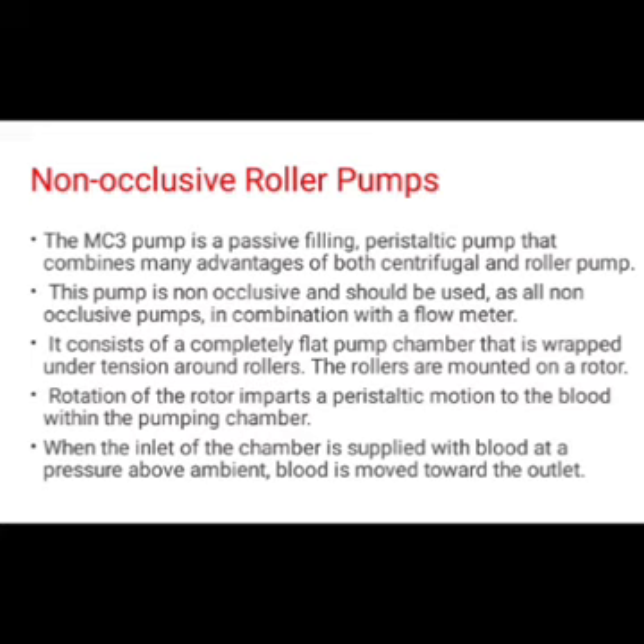Non-occlusive roller pumps. The MC3 pump is a passive filling peristaltic pump that combines many advantages of both centrifugal and roller pumps. This pump is non-occlusive and should be used, as all non-occlusive pumps, in combination with a flow meter. It consists of a completely flat pump chamber that is wrapped up under tension around rollers. The rollers are mounted on a rotor. Rotation of the rotor imparts a peristaltic motion to the blood within the pumping chamber. When the inlet of the chamber is supplied with blood at a pressure above ambient, blood is moved toward the outlet.